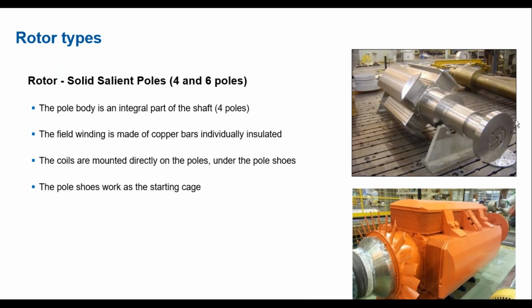Just to show you the physical construction, you can see the shaft, the rotor, and the pole shoes are all machined from a solid piece of steel. One additional consideration for these types of machines, the solid integrated pole shoe design, is that although they have a high starting torque, they do get a lot of heat buildup on the surface of the pole shoes. And so for multiple starts, we need to take that into consideration to ensure that the rotor does not thermally exceed its own capability.